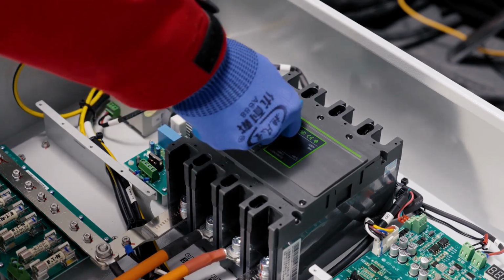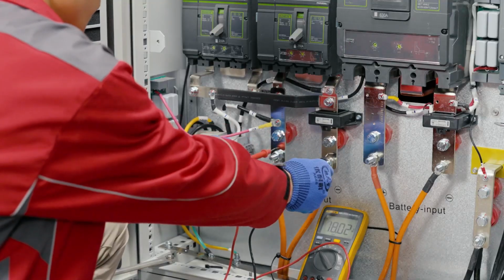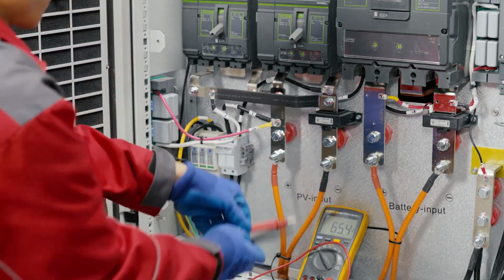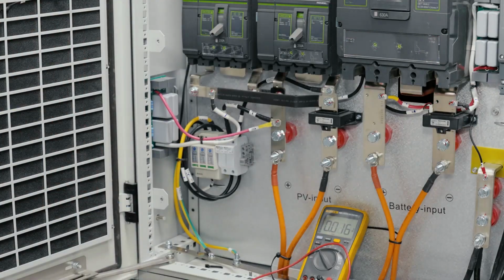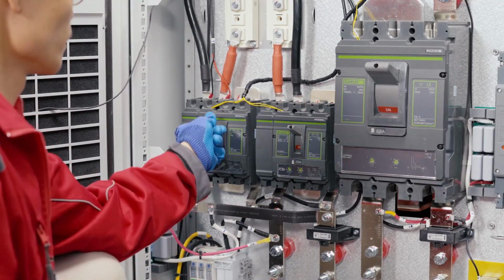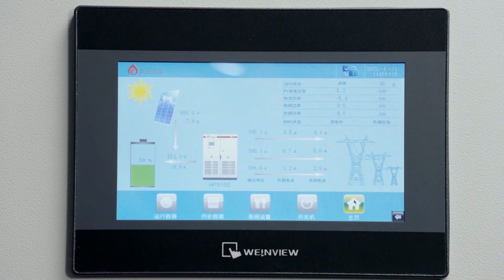Close the combiner box breaker. Use a multimeter to measure PV input for polarity, voltage level, and ground fault. Close the PV breaker of HPS. Set the charging current to verify whether PV can charge the battery.